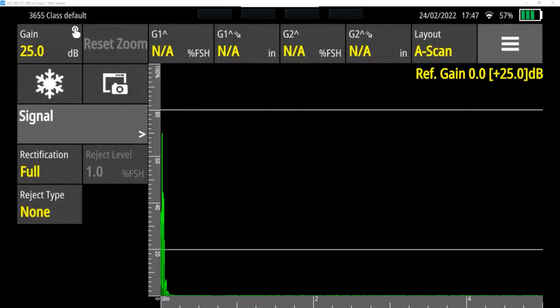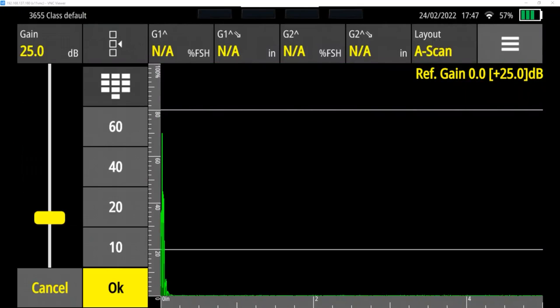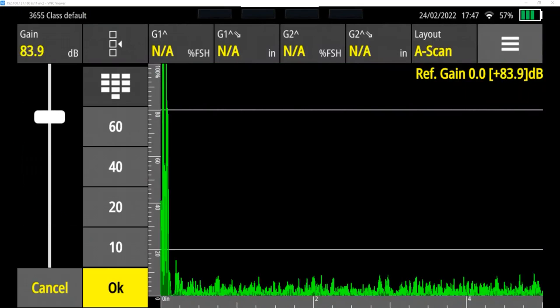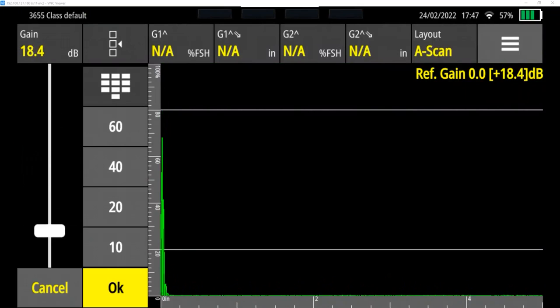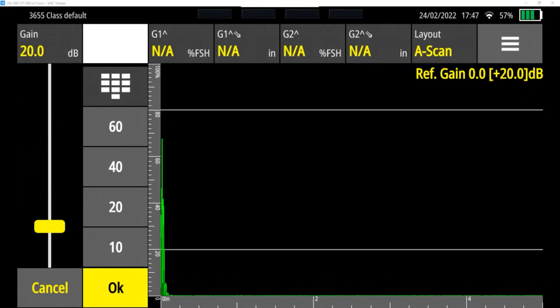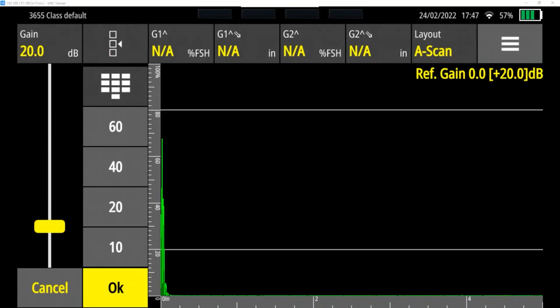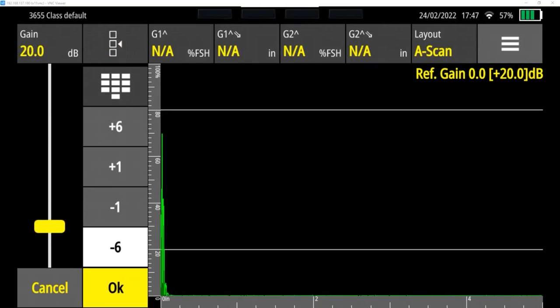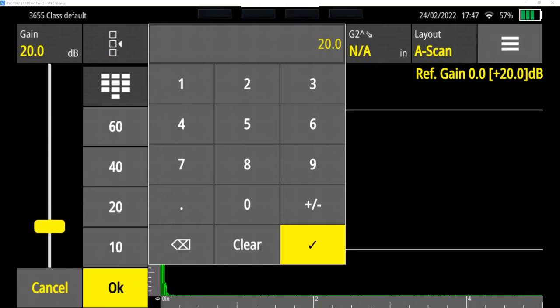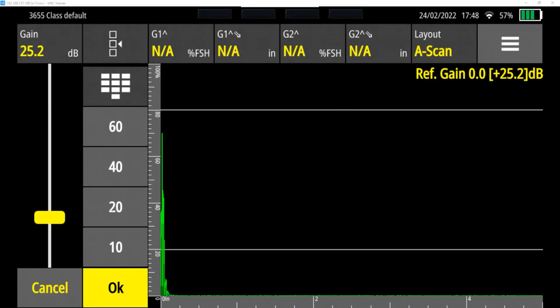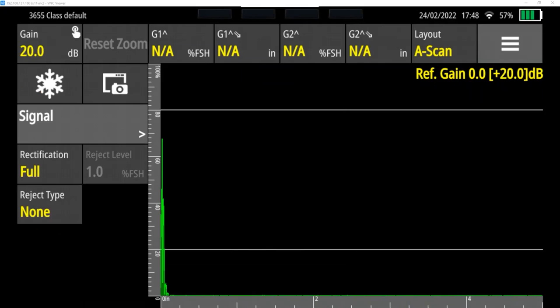And that will bring up an ultrasonic testing screen. A few features here. On the top left, we can adjust gain by tapping on it, and it brings up a menu, and this is to show how some of these different menus work. There's three different ways I can set the gain level here. I can drag the slider up and down. I can tap some preset levels, which there is by tapping the button at the top with the three boxes. I can change what's shown here. So I can do preset levels, or I can increase and decrease it by given increments. Finally, if I know a certain level I want to be at, I can tap the button that looks like a keypad, which will bring up a keypad. And now I can type in specific gain that I want. And those control menus are fairly similar, no matter which control it is you're adjusting.